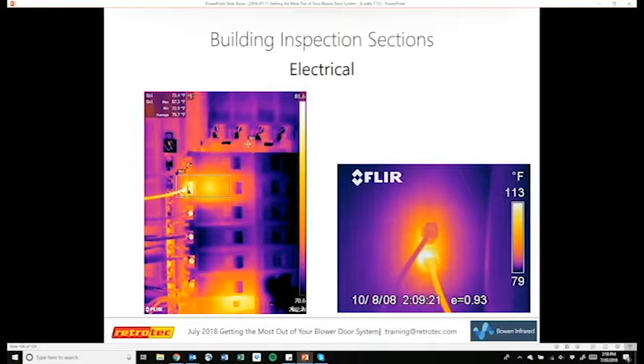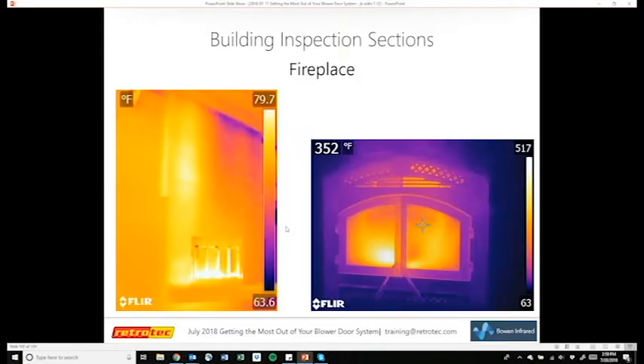Electrical systems, looking at breaker panels, breaker terminations, all of these are very doable in the thermal world. Here we have a simple receptacle with a cord plugged into it, and we have excess heat at the cord attachment point, which could be a receptacle problem or a cord problem, but very doable with the thermal camera. A little harder to determine on the electrical what's valid or not, because those things get normally warm.